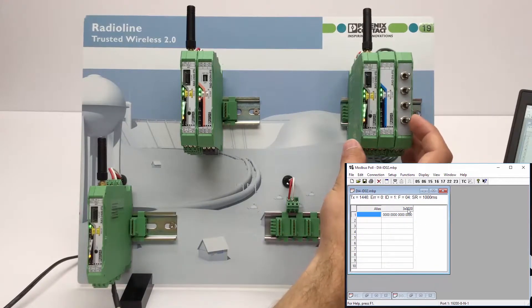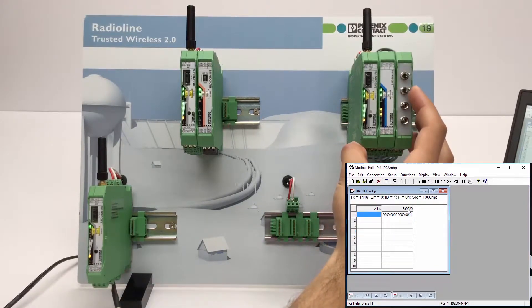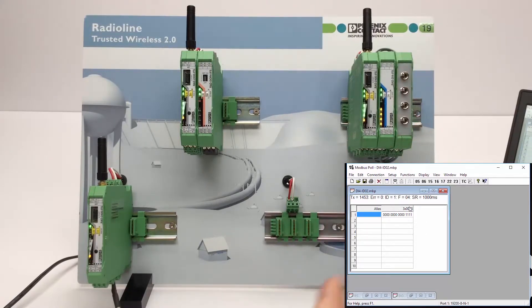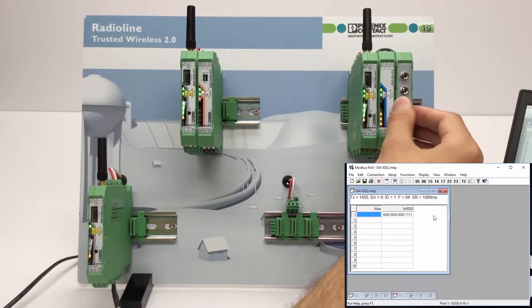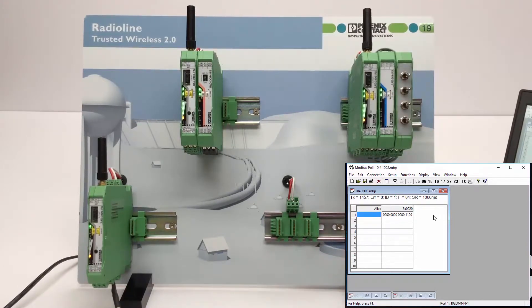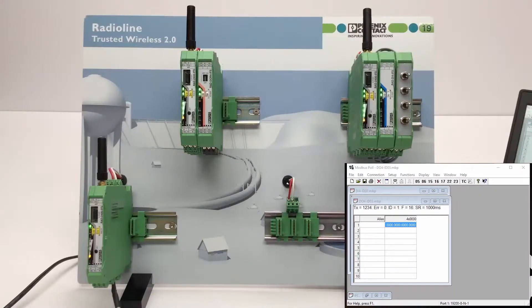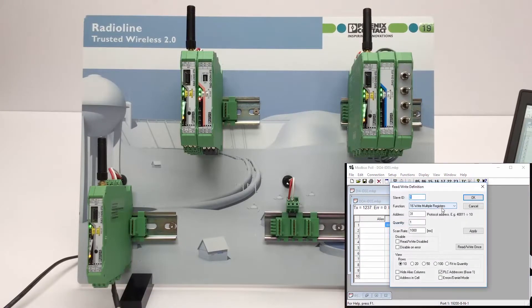The address range is already defined by function code 04, so we only need to enter register 21 to read the digital inputs. By setting the digital inputs DI1 to DI4, the binary register values change from 0 to 1. If the white thumb wheel of an output module is set to I/O map address 03, the process data is stored in the register with address 40031. To address an output module, Modbus function code 16 is used to write the register. With function code 03, you can read back the status of the output registers.